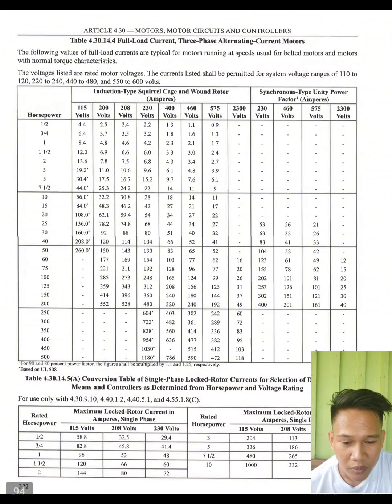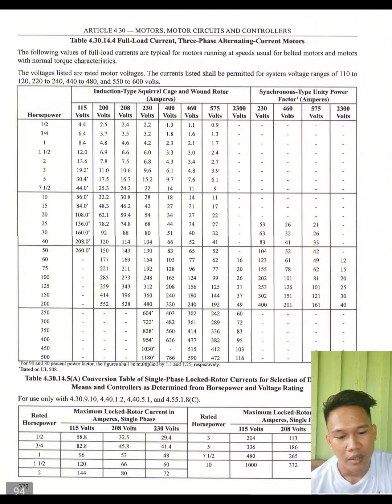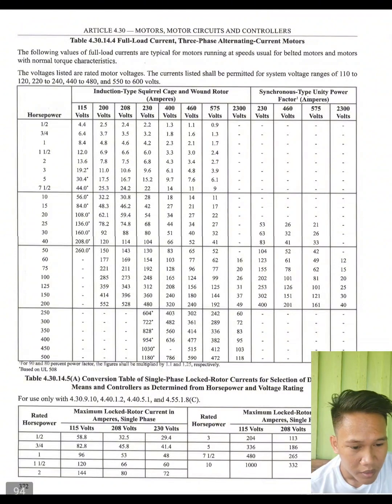So example ay punta, rated horsepower 1/2. So sa 115 volts, 9.8, 208 volts, 32.5, sa 230 volts, 29.4. Next is katong rated horsepower sa 3, ngayon sa maximum locked rotor amperes, sa 115 volts, 204, 208 volts, 113, 230 volts, 102. Sa 5 rated horsepower, sa 115 volts, 336, 208 volts, 186, 230 volts, 168. Then sa rated horsepower sa 7 and 1/2, sa 115 volts, 480, 208 volts, 265, 230 volts, 240. Then sa rated horsepower 10 horsepower, sa 115 volts, 1,000, 208 volts, 332, 230 volts, 300.